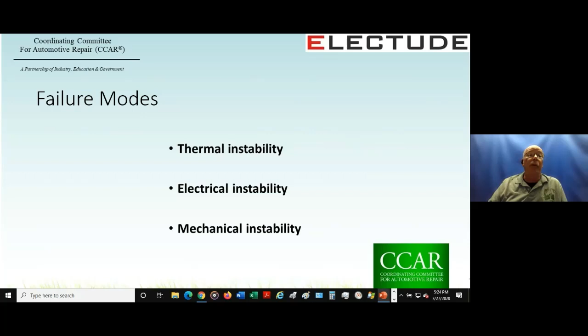To further understand thermal runaway, it's essential to grasp this concept also, and that is that heat generation increases exponentially within the battery with temperature, while heat dissipation, or the ability to cool it, it says increases, but that's just because it's on a plot, is linear or gradual over time. The response to any failure mode scenario arises from the dynamics of heat generation and heat dissipation over time.